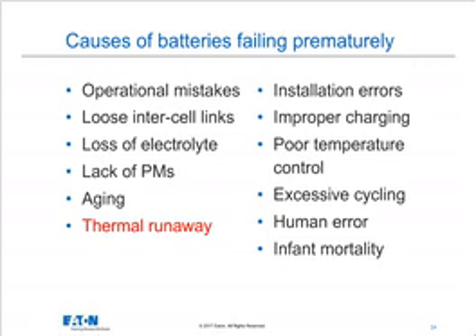Well, when the battery draws more current, that makes it get hotter, which makes it draw more current, which makes it get hotter and draw more current and get hotter until the next thing you know, you have a fire. And this is a definition of a bad day in the battery world. So one of the primary reasons for having battery monitoring is to detect, mitigate, or prevent thermal runaway conditions.